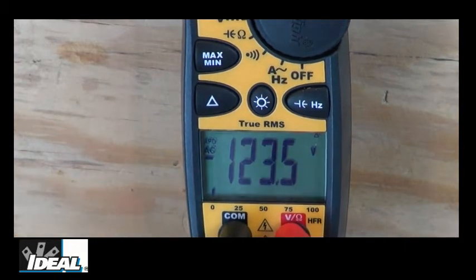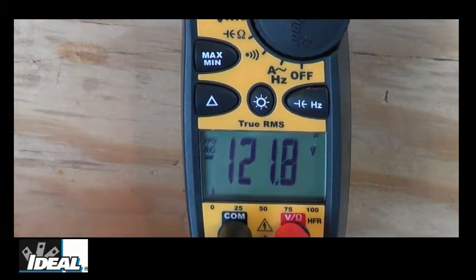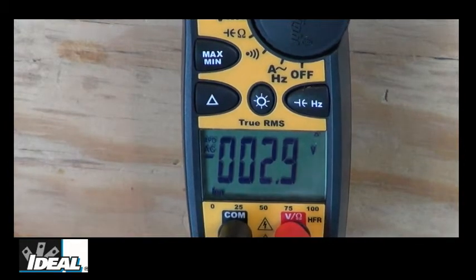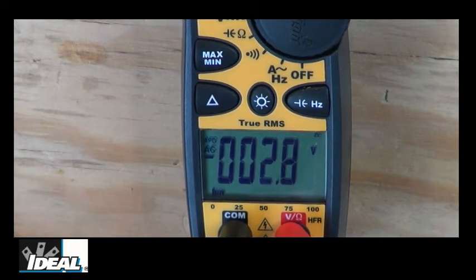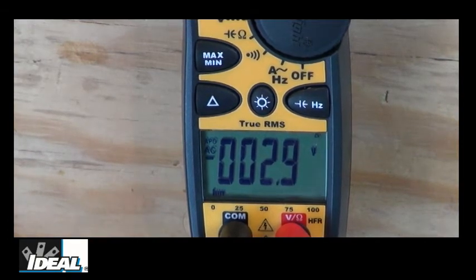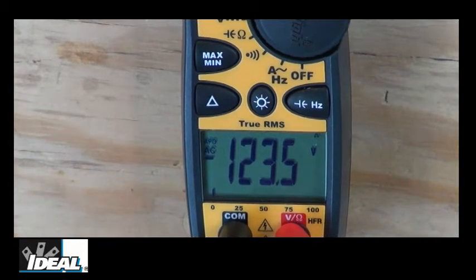Now, if I plug these test leads into another extension cord over here on the other side of this countertop, it's actually going to give me another reading, but it's only going to give me the differences in the two readings. And we're reading about 2.9 volts difference between those two outlets. And so that's another nice feature of the tester we can use in many applications throughout a building.